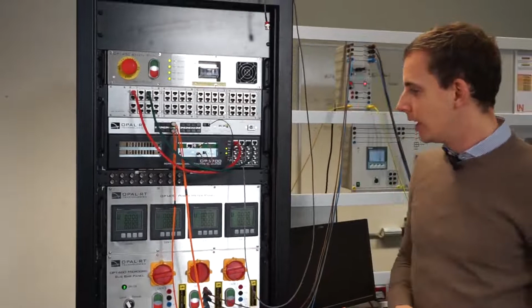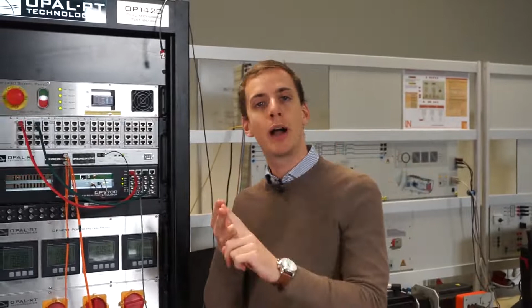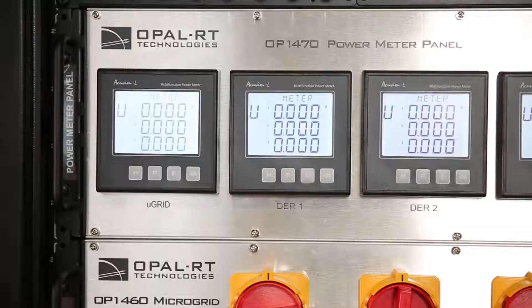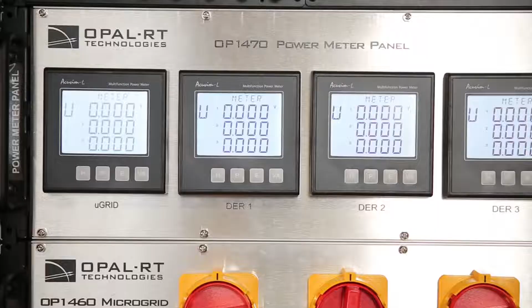Another interesting component, the power meter panel, allows measurements to be displayed on the fly, such as voltage, current, active power, reactive power, apparent power, power factor, total harmonic distortion. And we can benefit from these measurements thanks to current transformers and potential transformers connected to the 4 microgrid bus bar DER connections.